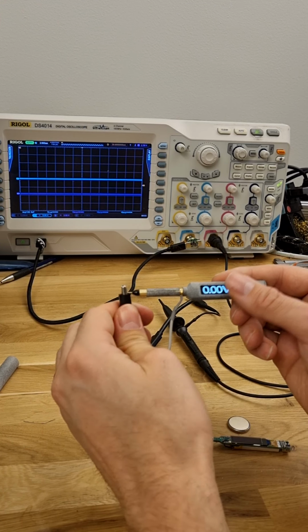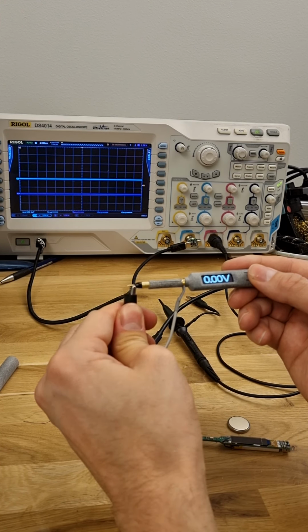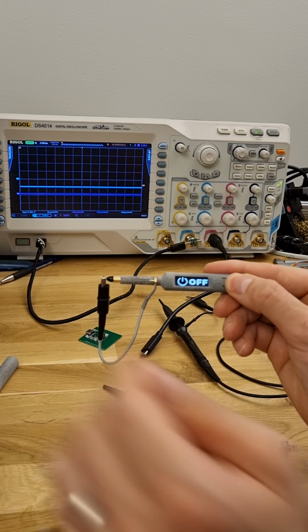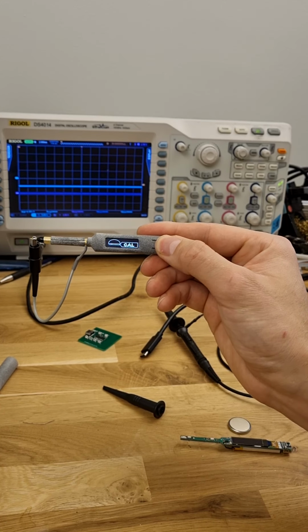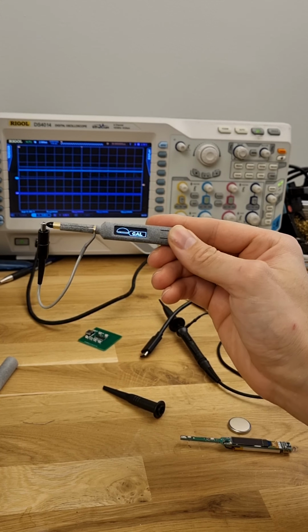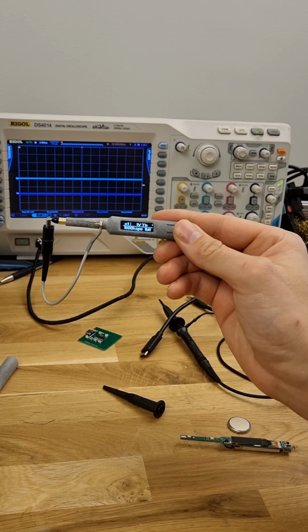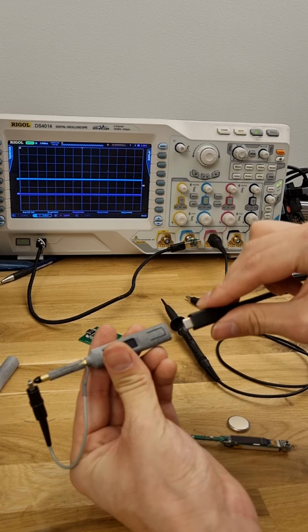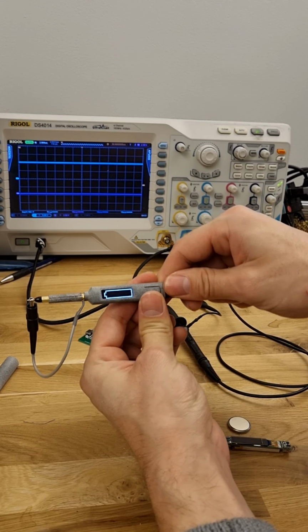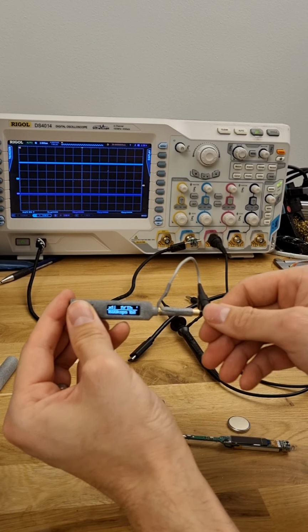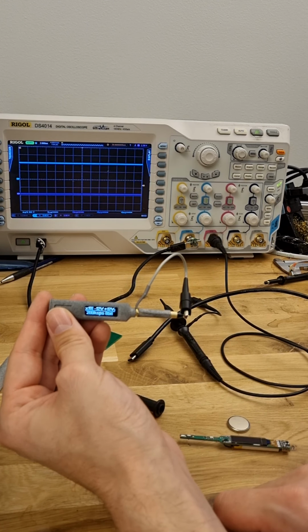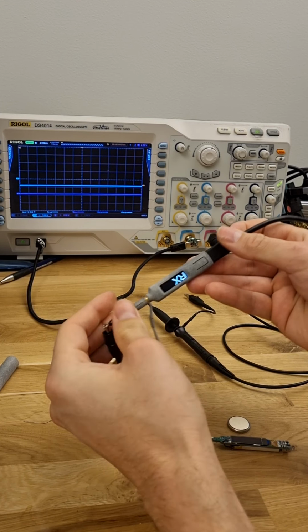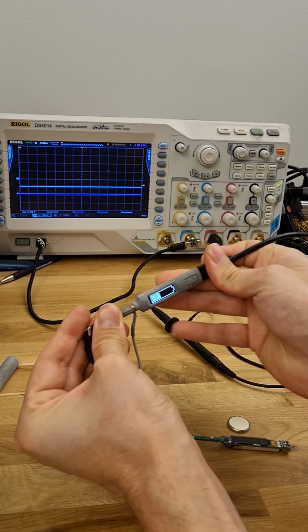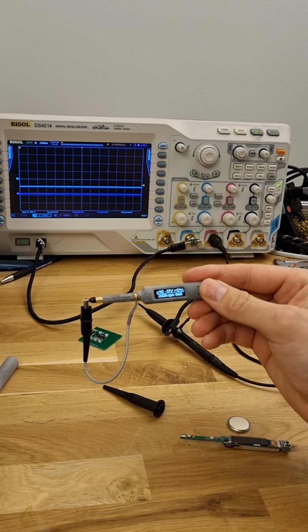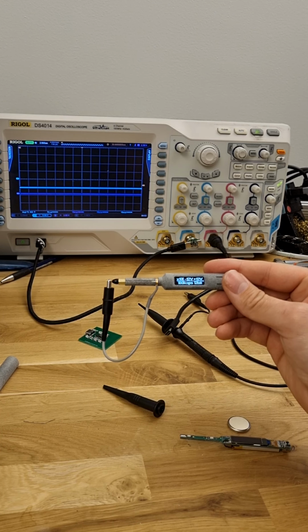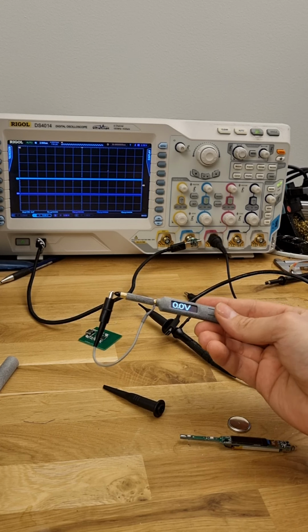You can also do calibration. So if I connect this short, turn it off, and then when I turn it on, I hold the power button. It's calibrating itself. It's offset calibration. And you can also change between left-handed and right-handed. So now it's left-handed mode. You do that by plugging in the charging and pressing on the button. Then it changes between right-hand and left-hand mode.